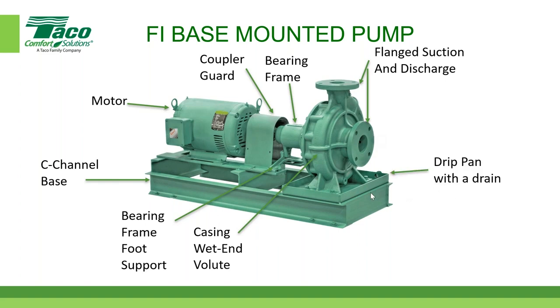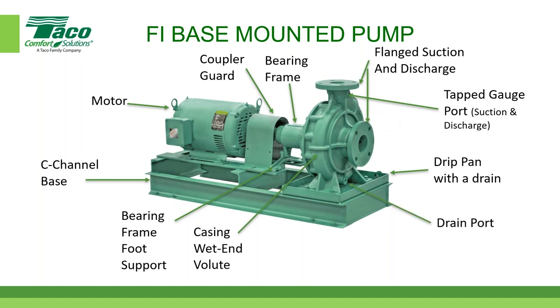Drain pan with a drain, drip pan with a drain. And it extends out far enough so it catches any dripping here that might occur so it doesn't just go down onto the floor. Another thing that our pumps have, and I'm only showing one picture here, but there is another one down below, tapped gauge port for suction and discharge. So you can install, and there'll be a picture later where the pressure gauge is installed right through that port. So that's available as well. And one of the last things I'll point out is there is a drain port on the bottom. So pretty straightforward. So those are the components of a base-mounted TACO FI pump.